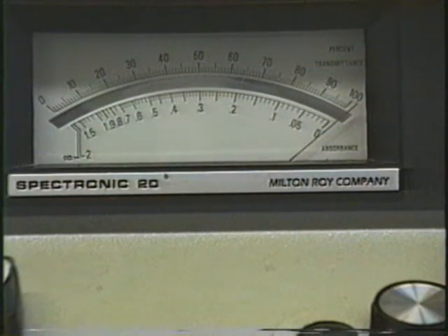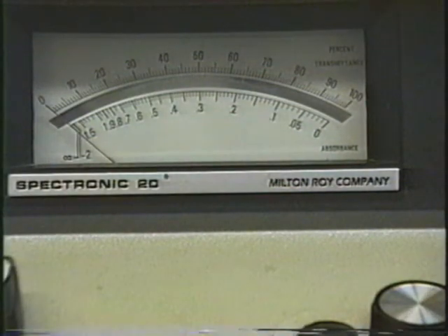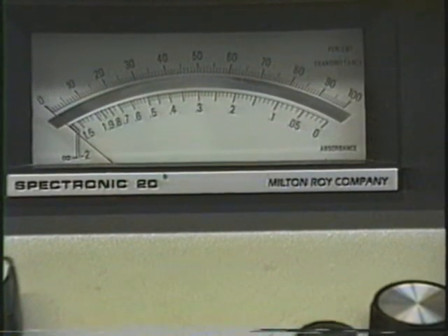So let's put it in here and see what it reads. Now we don't do any more adjustment, we just read. And you see it's reading a little over 100%, so we'll have to estimate. I would say that's 102%, 102.0%. Now, you'll go through everything we did a second time to make sure everything is reading right. Then you will go back and make a solution and bring your solution to the spectrometer. Let's do that now.